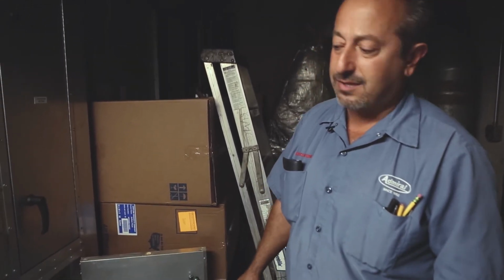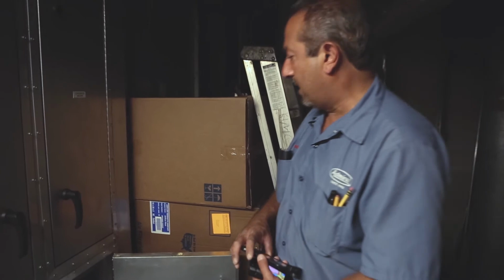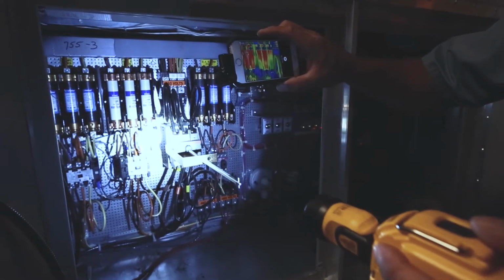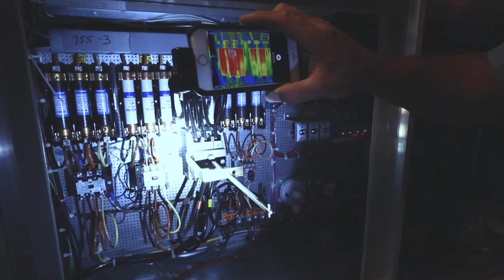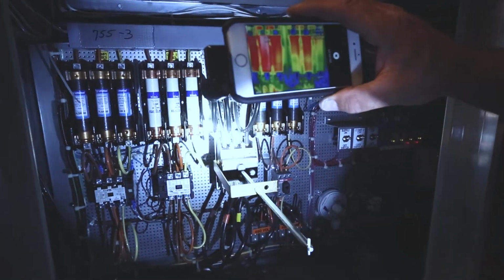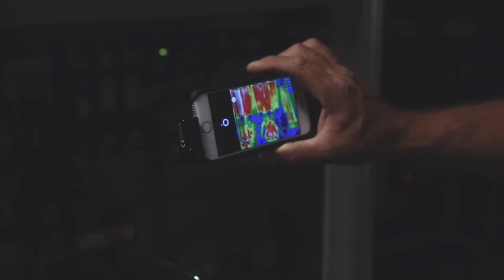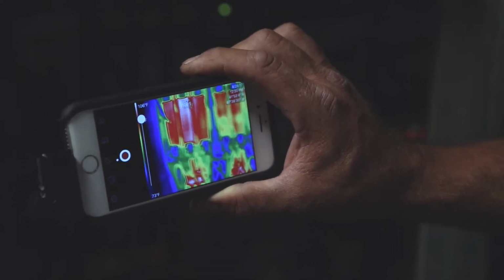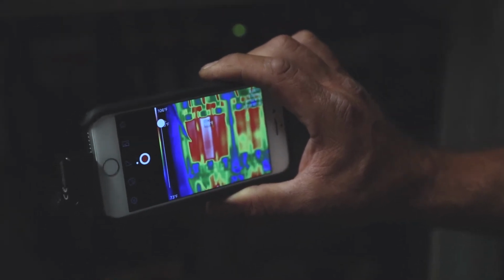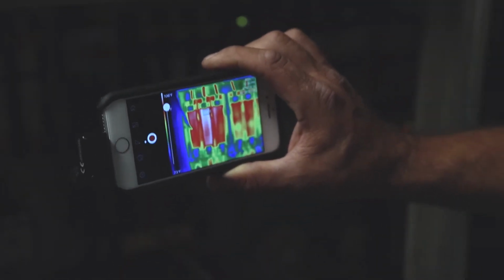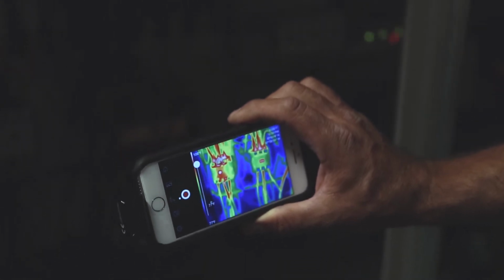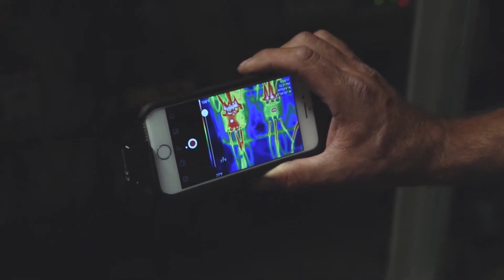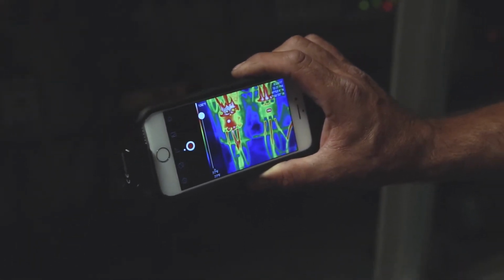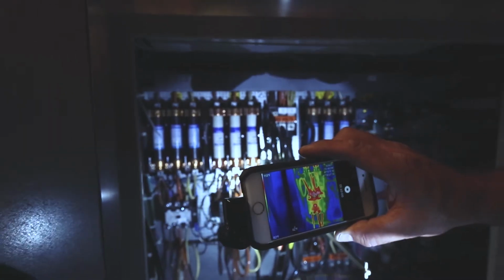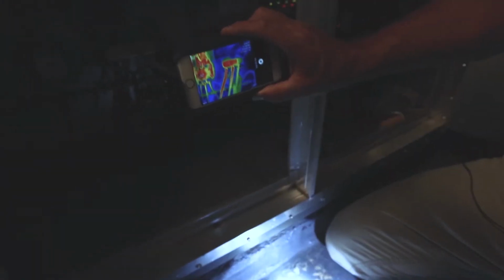So let's get started. Here's a control panel. Basically we have two contactors that disconnect, some fuses. I'm gonna scan. Here's the one off the phone. As you can see, left, 3 fuses. You see that difference in temperature on the center one especially. We have an issue with possibly a loose wire. We scan down, look at the difference in the contactor. Definitely an issue on our left wire.